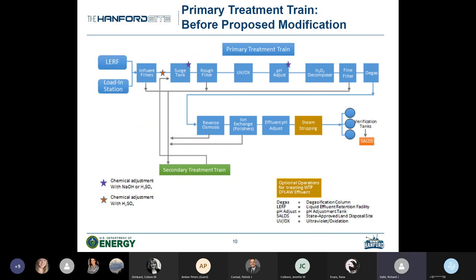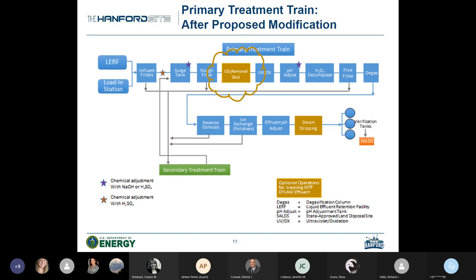This slide provides a frame of reference for the existing primary treatment train. The UV ox unit is called out right in the middle of the primary treatment train, and the D-gas column is at the back end of that first row. The UV ox call-out is important because we want to manage the negative impact to its unit operations, and the D-gas column is the existing CO2 removal capability we currently have. The next slide shows the proposed installation — a CO2 removal skid placed ahead of the UV ox — showing where that fits into the flow sheet.